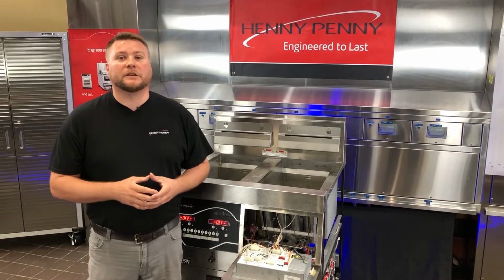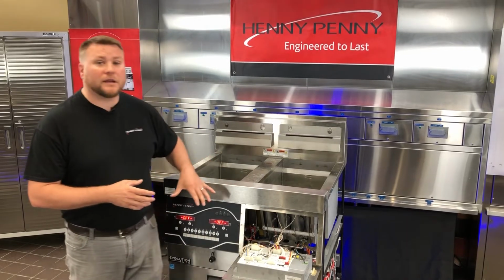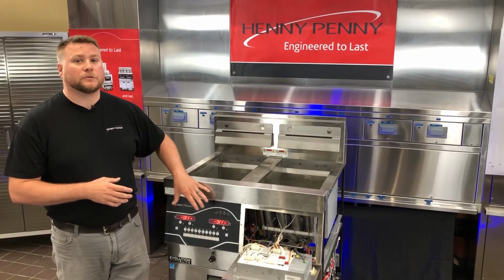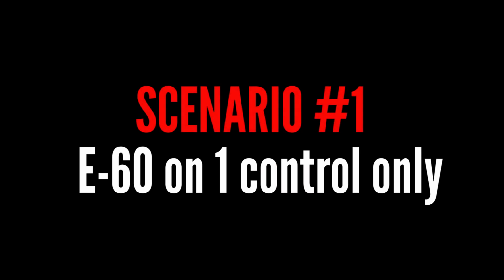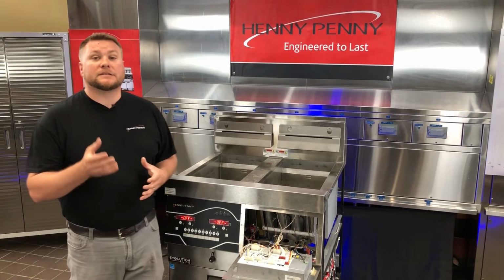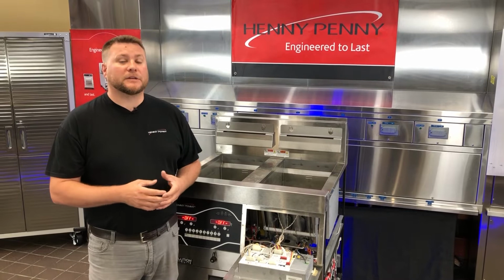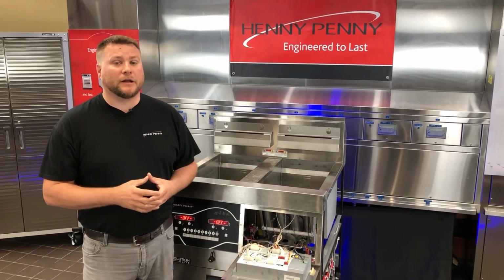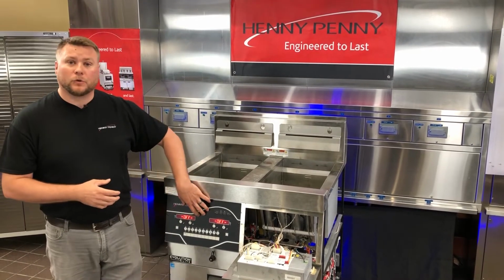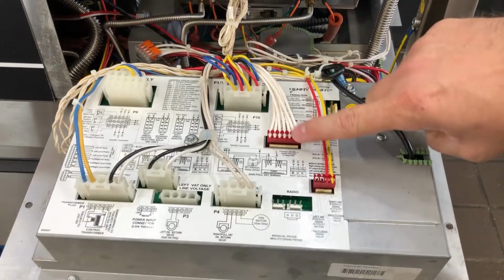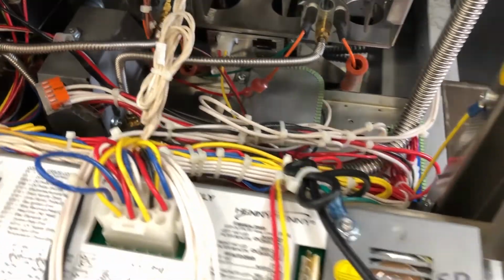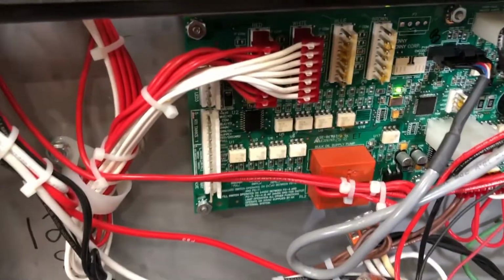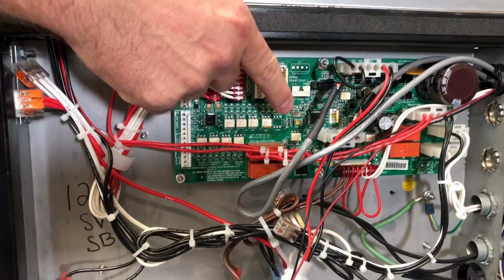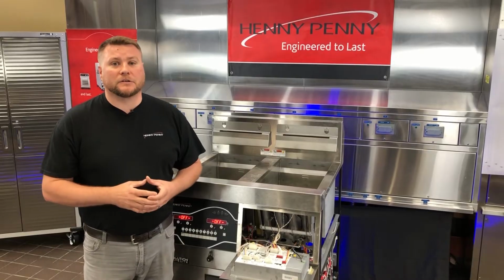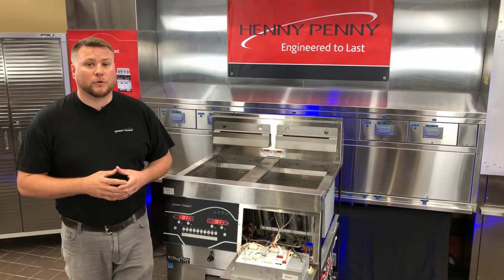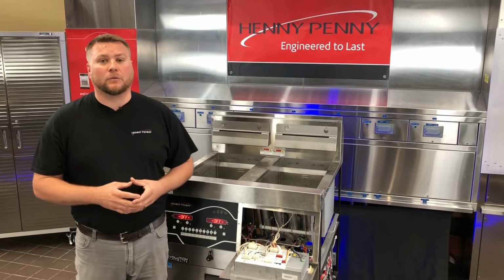Let's talk about troubleshooting the E-60 when it comes to having that error code on one control panel only. This is very simple because it can really only be one of three items: the control board, the communication cable that goes from the control down to the AIF board, and the AIF board itself. It's very rare that we actually find the AIF board to be faulty, but it's something we don't want to rule out.